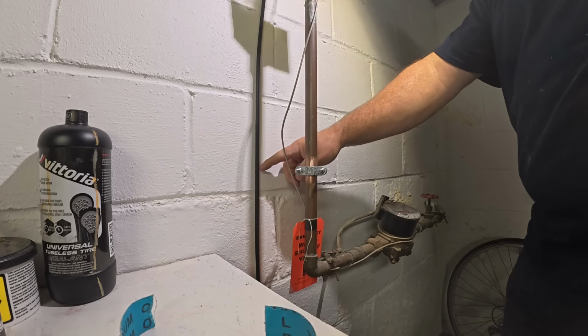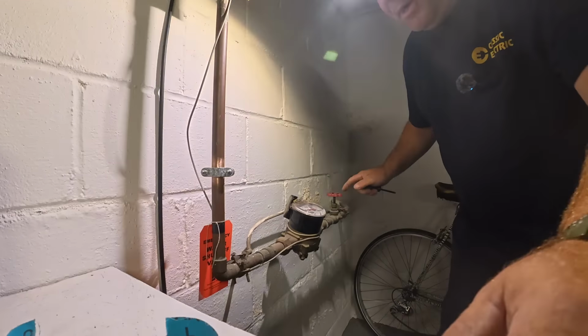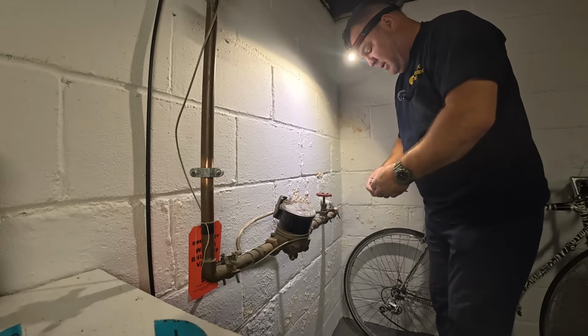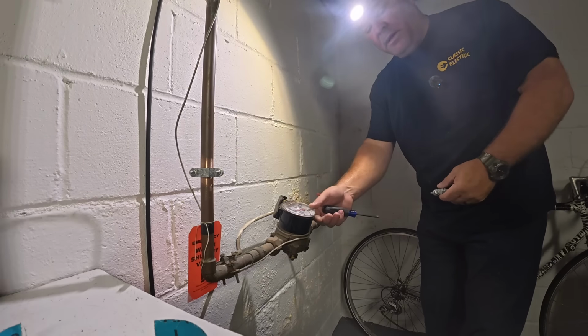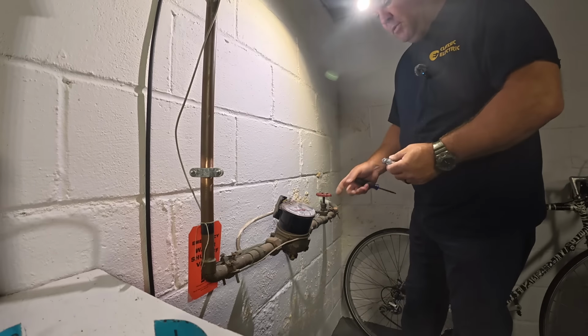We'll strip away this number 2 after we clamp it to the wall. The reason it's important to jump out to the other side of the pipe is because should this water meter be removed for whatever reason, you will lose your ground.